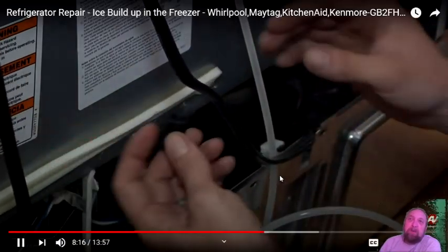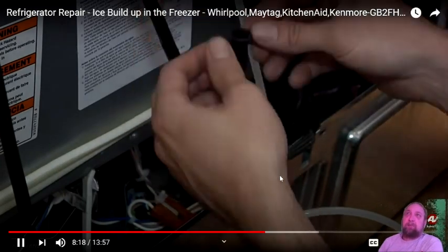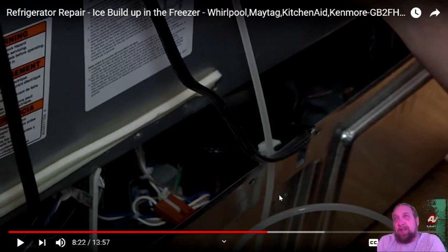Now some of them build up with algae. It slides onto the drain line. It's going to go basically front to back, facing. Now, the reason why it's closed up like that is because what they're trying to prevent is warm air from down here going up into the freezer. That'll create excessive frost. So that device is like a check valve. It lets water come out, but it tries to prevent warm air from coming in.